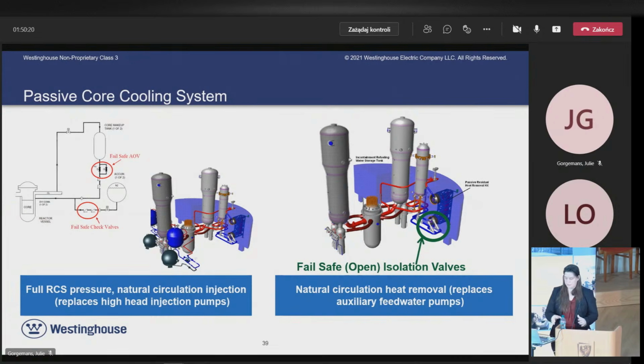To remove heat from the reactor coolant system, so decay heat as well as stored heat, we also use a dedicated heat exchanger, which is located inside containment. And it's based on the same design as the core makeup tank in terms of how we ensure that we have flow through that heat exchanger. We again have an inlet line connected to the reactor coolant system and thermally insulated, so staying hot, while the outlet line is non-insulated and so will dissipate any heat, so being cold. Once the isolation valves open, it will flow and create a natural circulation through the heat exchanger.